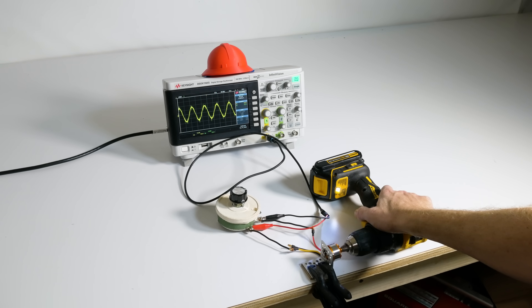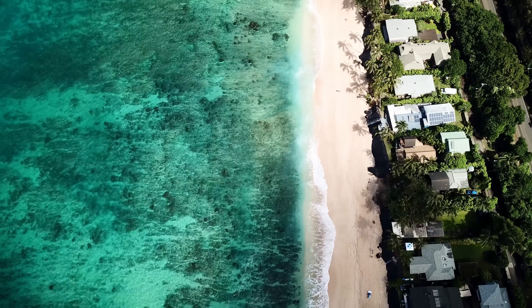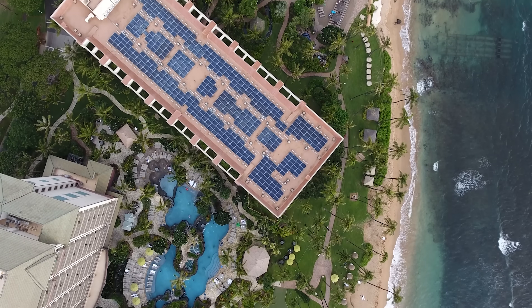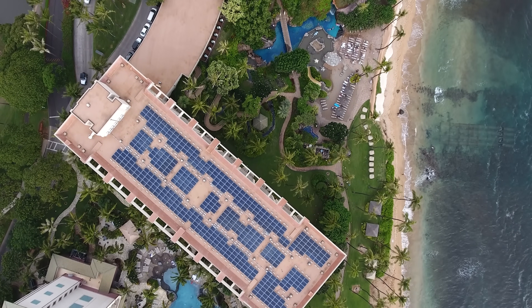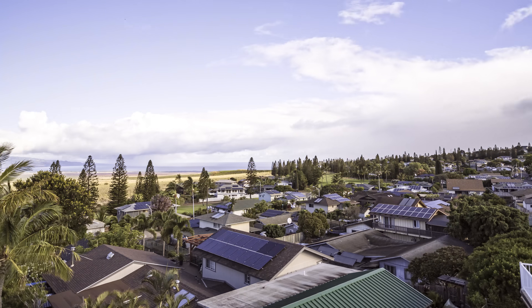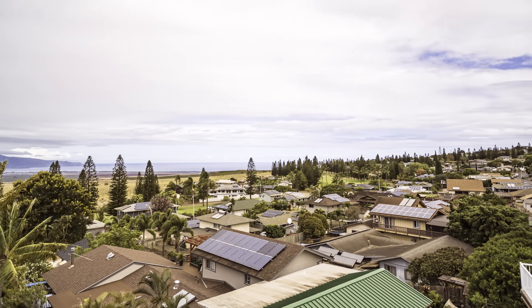About half of all renewable energy on the Hawaiian islands currently comes from small-scale solar installations, like those on residential and commercial rooftops — collectively known as distributed energy resources. This has the obvious benefit of bringing resources closer to the loads, reducing strain on transmission lines, and taking advantage of space that's already developed without requiring the utility to invest in new facilities. But distributed sources come with trade-offs. Most parts of the grid are built for power to flow in one direction, so injecting electricity at the downstream end can create unexpected loads on circuits and equipment not designed to handle it. Distributed sources also affect voltage and frequency, since something as simple as a cloud passing over a neighborhood can dramatically swing the flow of power on the network.